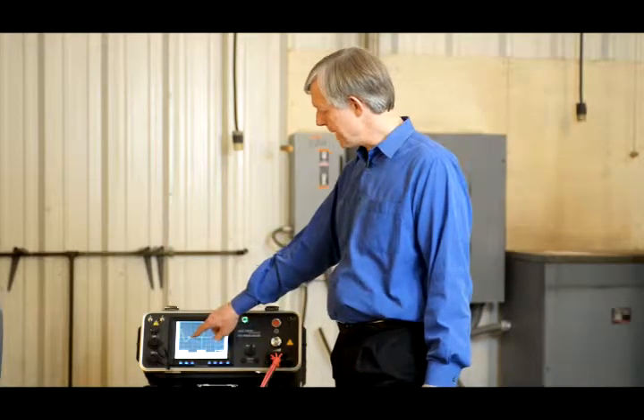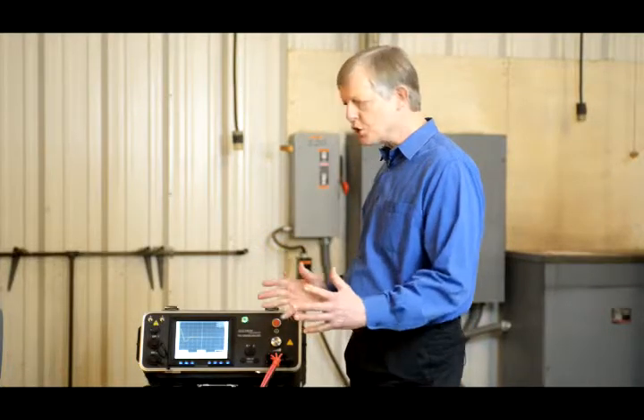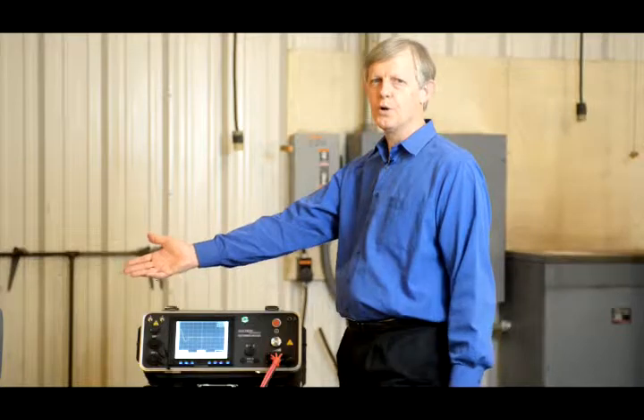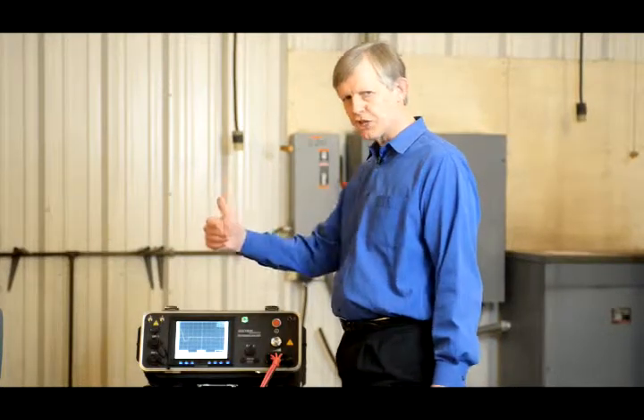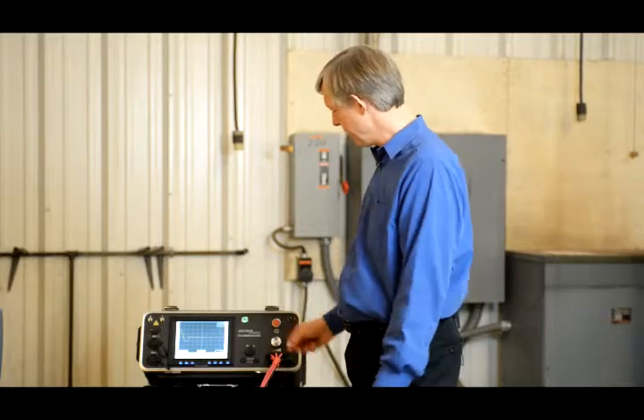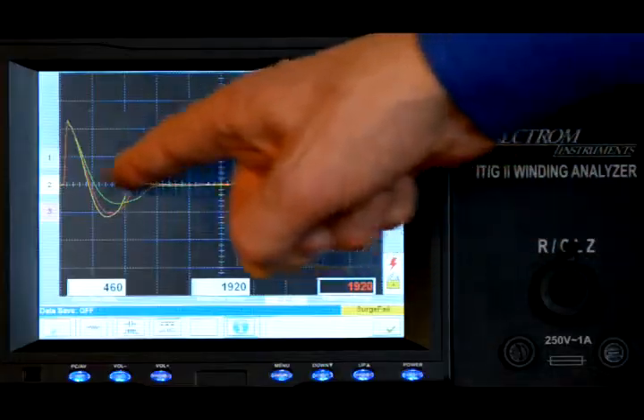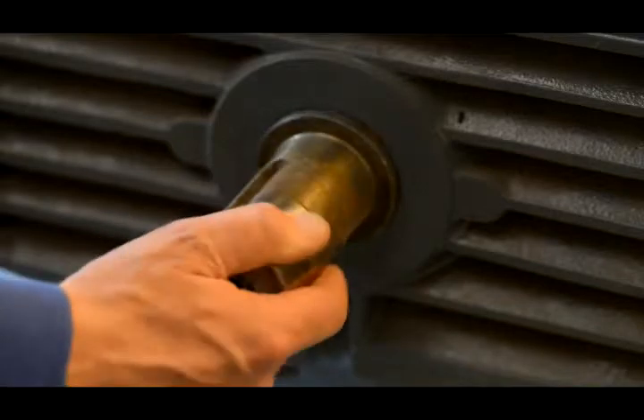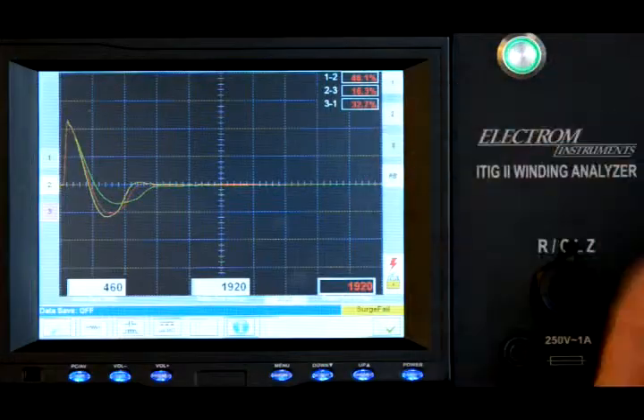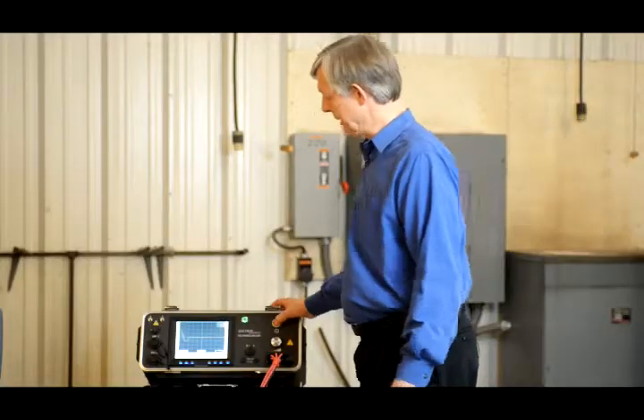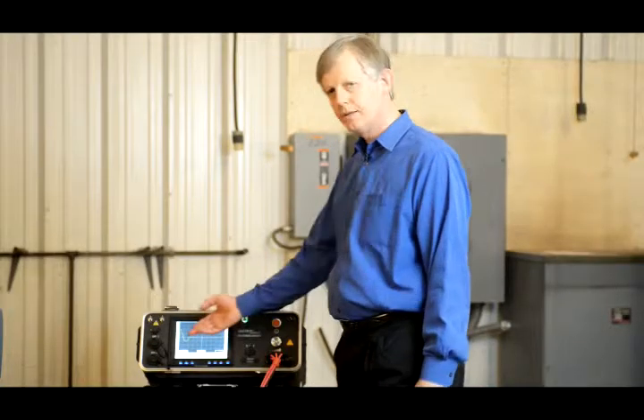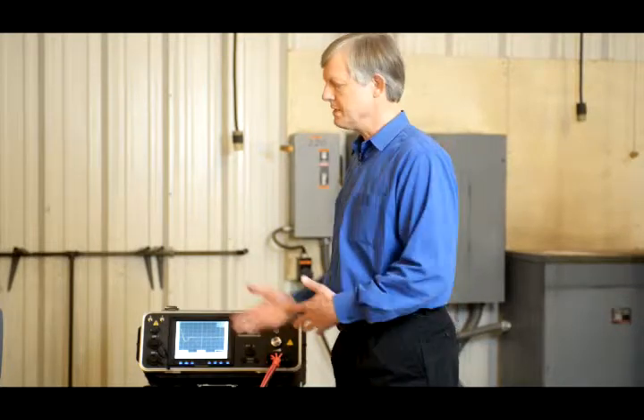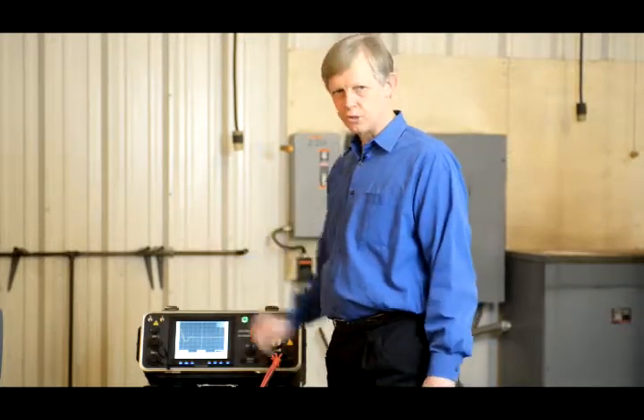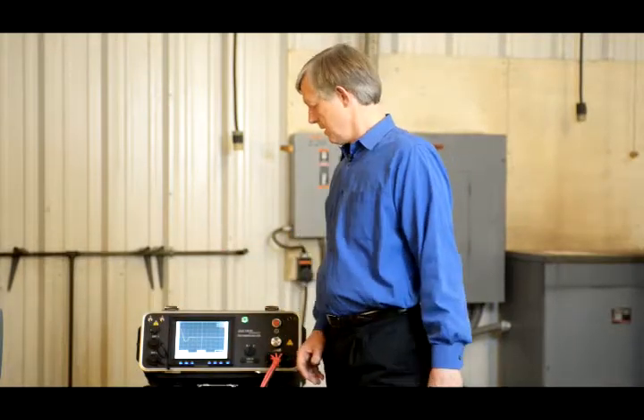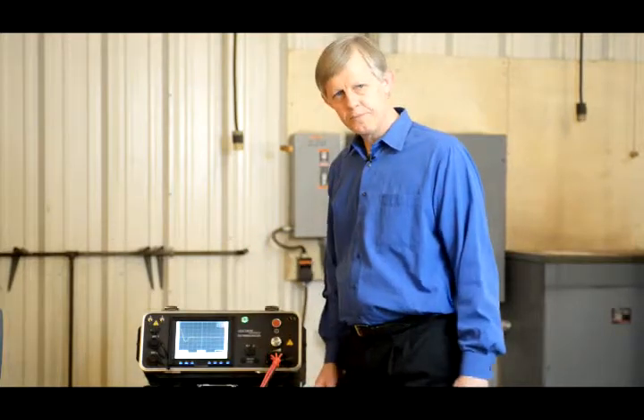We see that there is some slight separation. That could be an issue, but we also know that this is an assembled motor, and with an assembled motor we get rotor action and we'll get a slightly different frequency going from lead 1 through lead 3. We can now turn the rotor and repeat that last test to see if we can get the waves to line up, and they do. If you are familiar with testing assembled motors, you know that you need to turn the rotor to line up the waves to make sure that you have a good test. Let's call this one good.